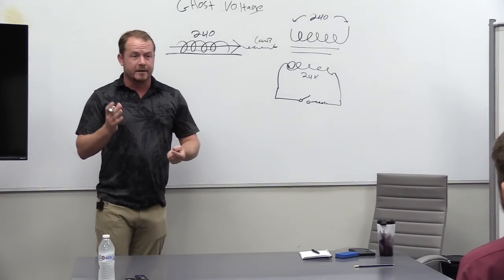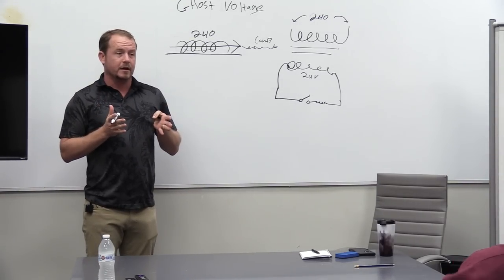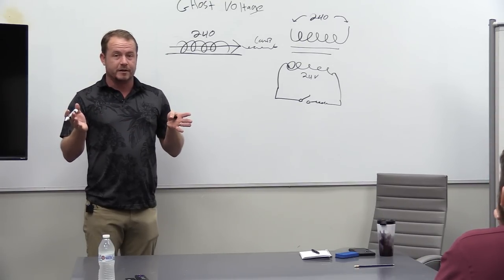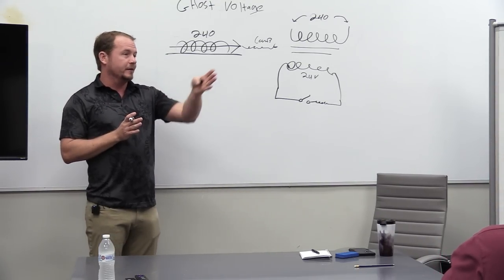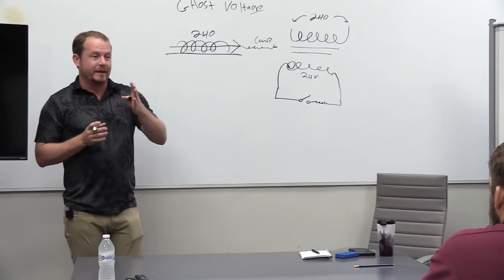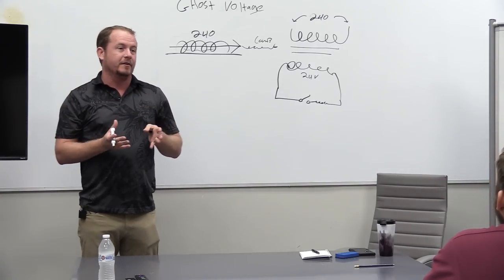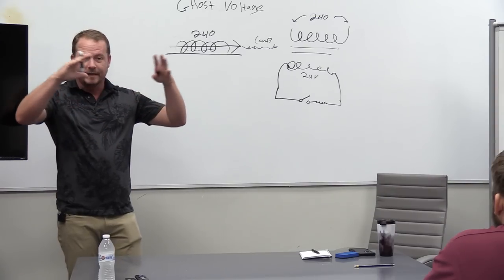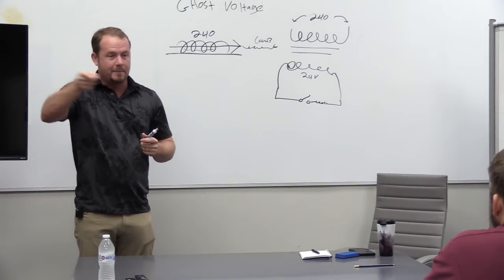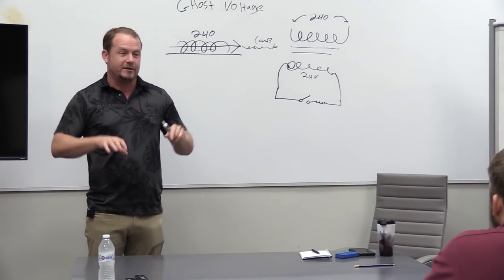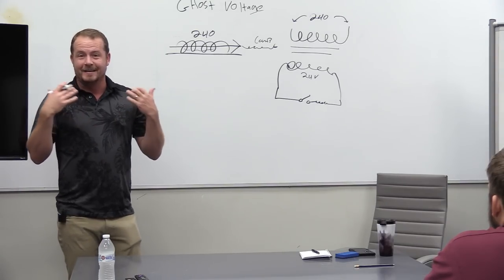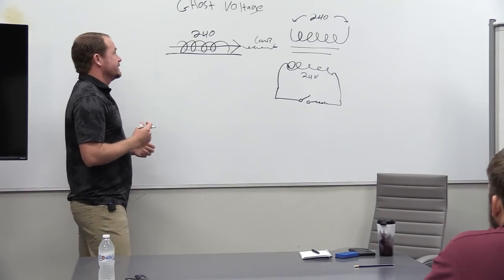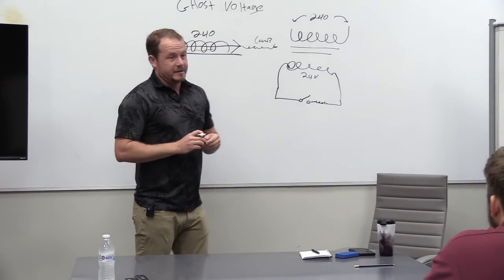One lesson is we don't want to run conductors next to each other, especially high voltage and low voltage conductors, especially control conductors. We don't want to run them through the same hole in the cabinet. When we're running them inside of an assembly, we don't want to lay them next to each other. We don't want to take wires and wrap them back and forth with just a bunch of extra and jam it right next to high voltage, because you're going to get that induction. So one of the sources of ghost voltage is induction.